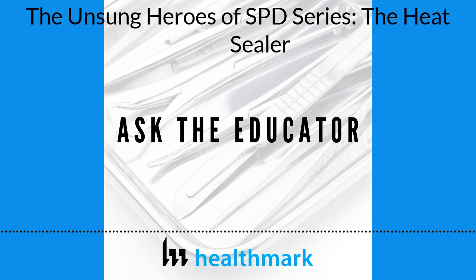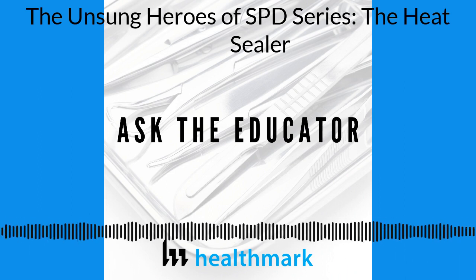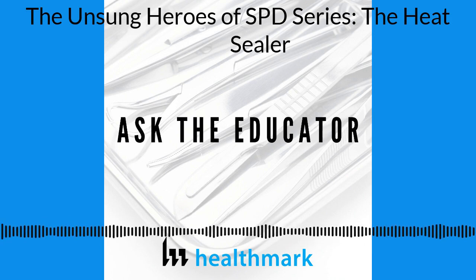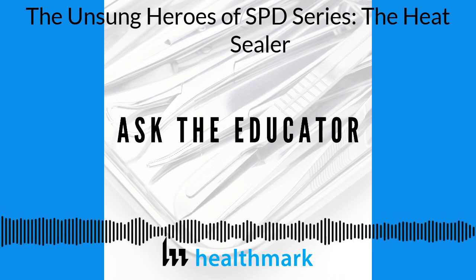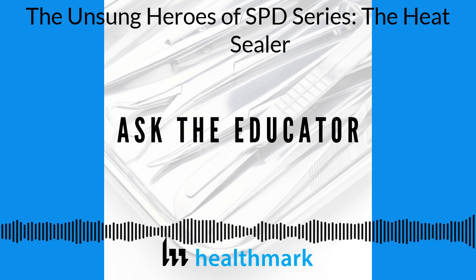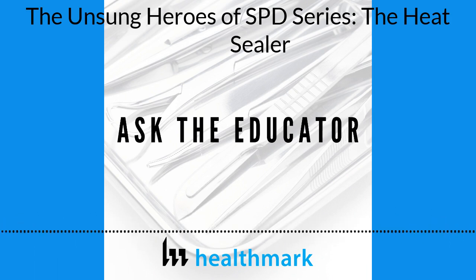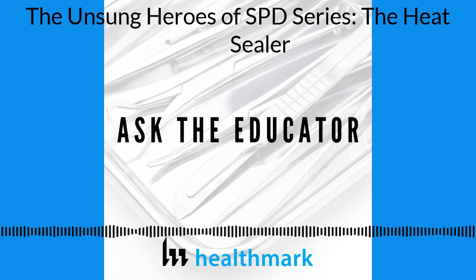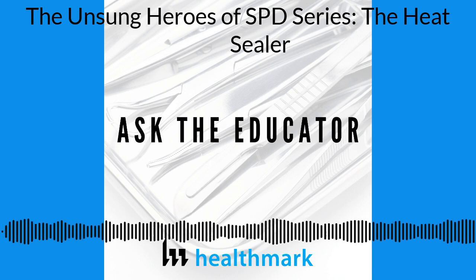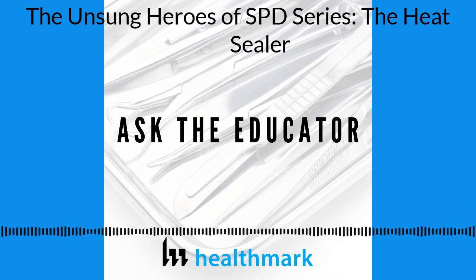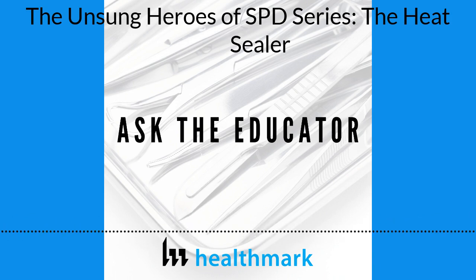So I believe to ensure a heat sealer is working properly, you need a QMS, quality management system, IQ, OQ, PQ. So we're going to make this part up. You just bought a new heat sealer. When it comes in, you should get your biomed department or technology management to come in and do the IQ and the OQ. Part of that OQ will be the tests that you'll eventually use, and to understand the preventive maintenance to ensure it's working properly, and to find independent testing to allow you to verify that the sealer is really sealing properly, whether it's Tyvek or non-Tyvek pouches.